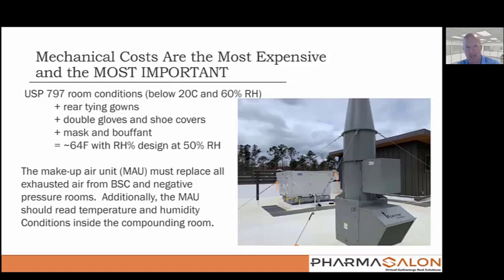Right, we call that a modulating compressor or a scroll compressor. But your existing piece of equipment that you have now only has a thermostat, which means it only reads temperature, and that's why a lot of these clean rooms around the country are not performing, because their air handling system only reads temperature and not humidity. And when you drive one down, you lose control of the other, and that's probably the biggest point that I drive home in my conversations with engineers. When you put people in rear-tying gowns, double shoe covers, double gloves, hair bouffant, and mask, 64 degrees in a clean room still may not be quite cool enough for employee comfort.